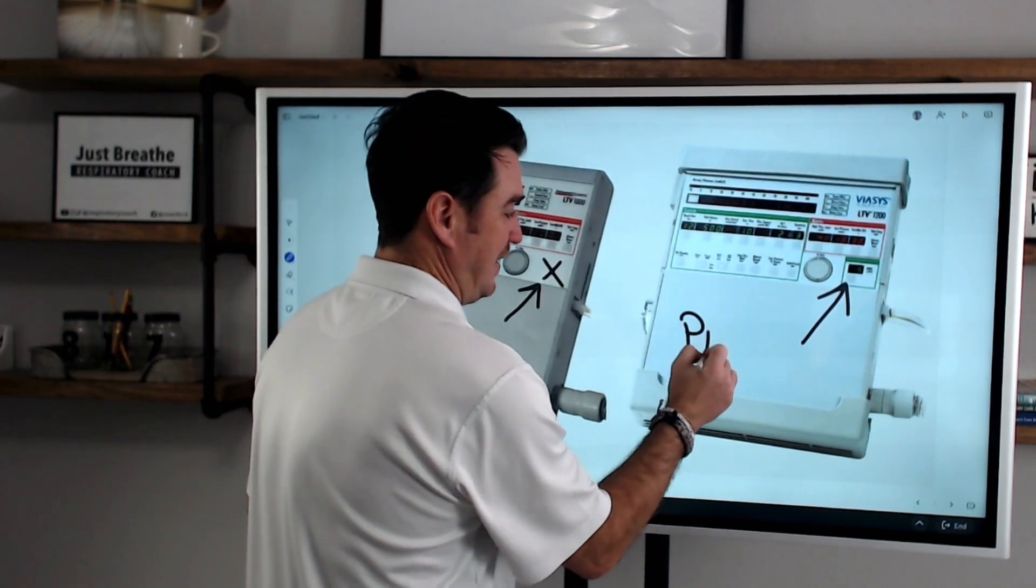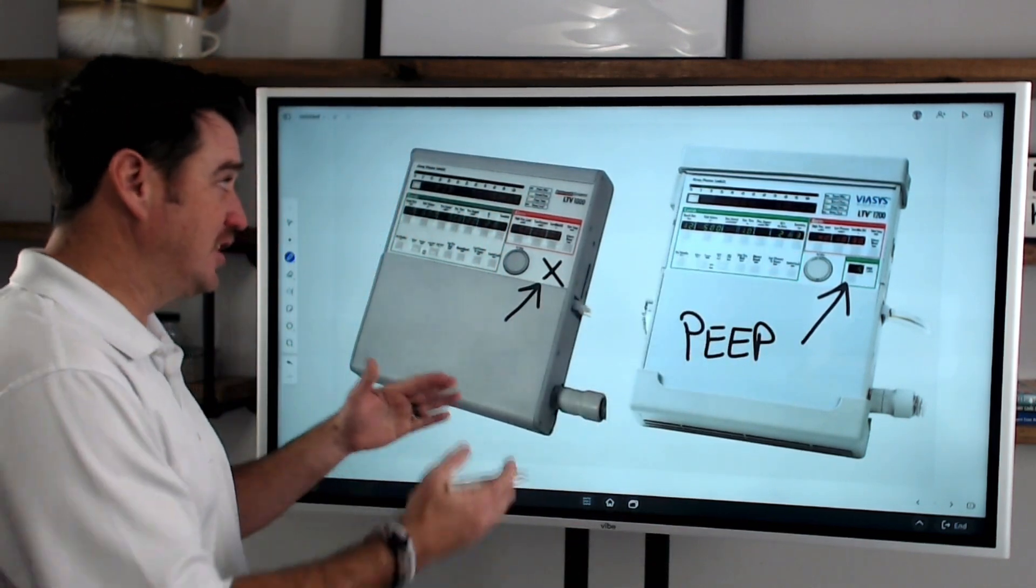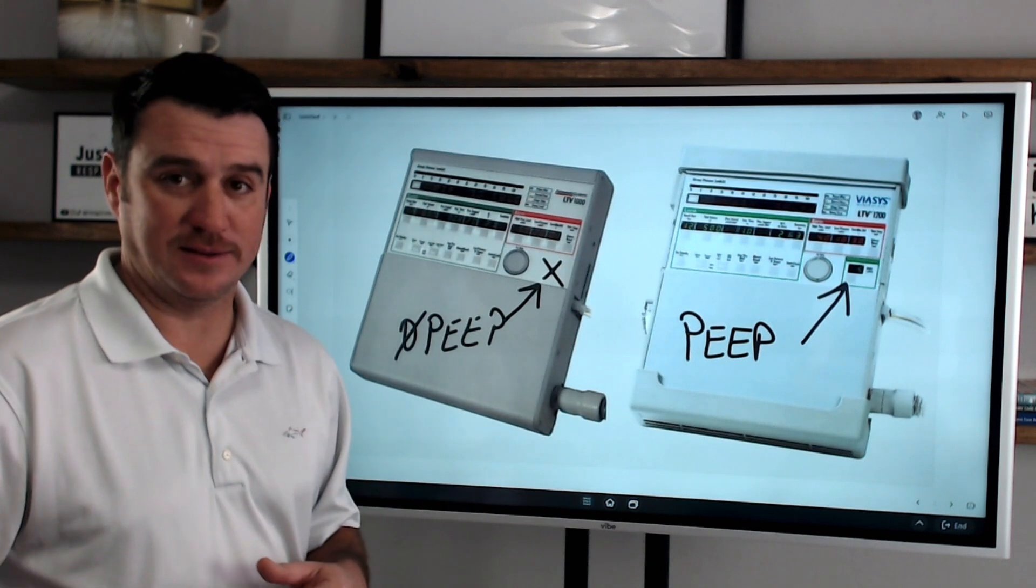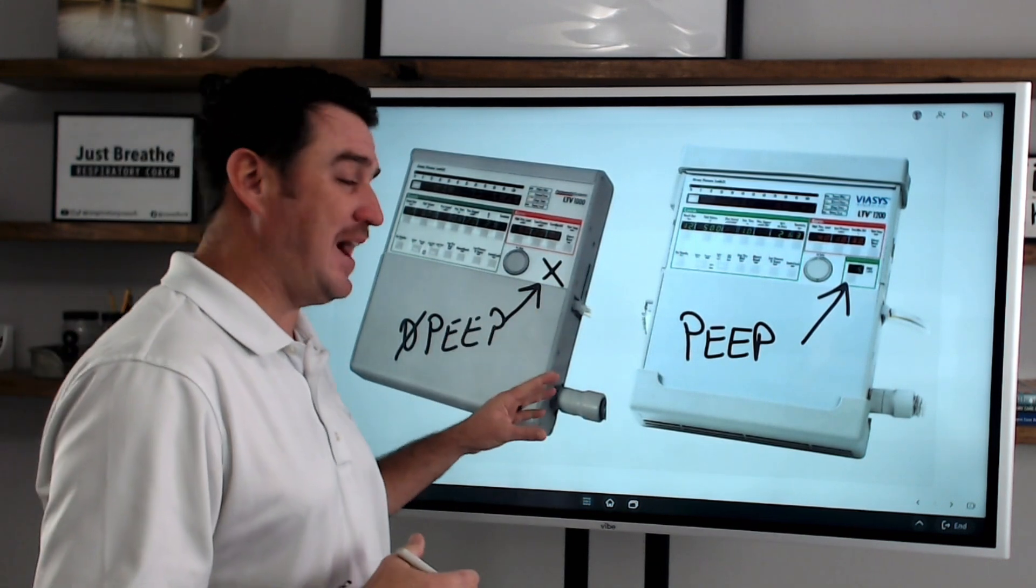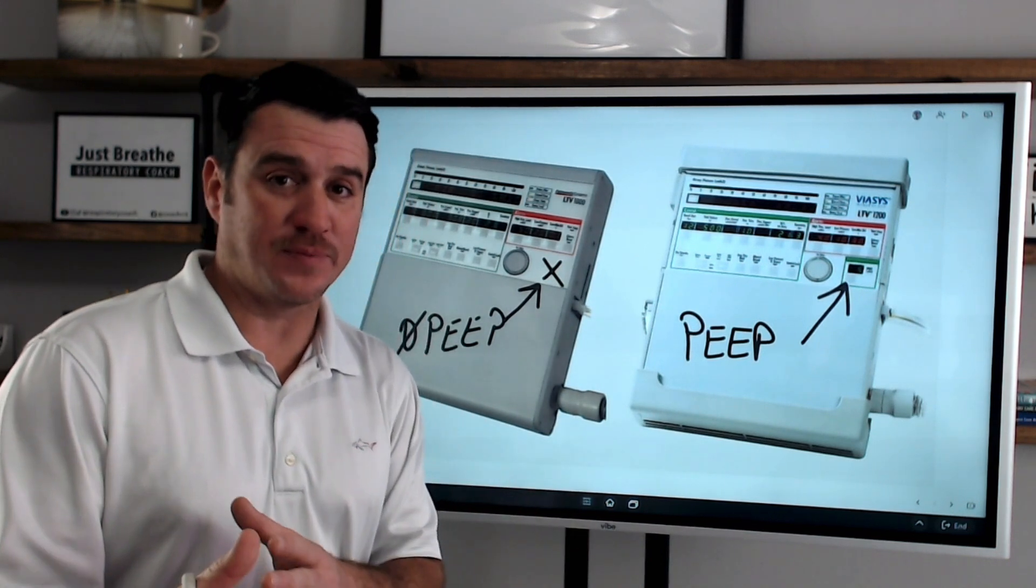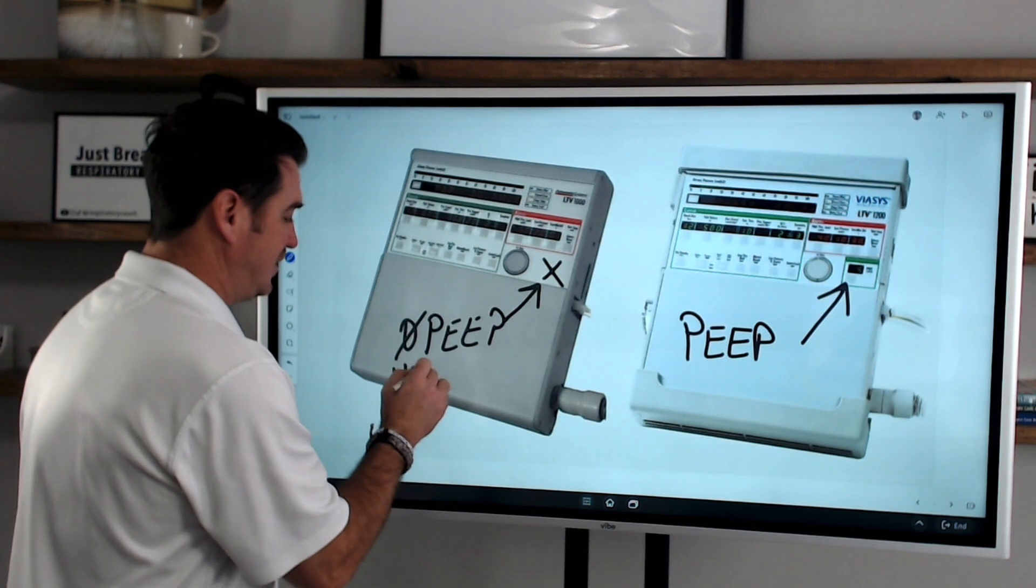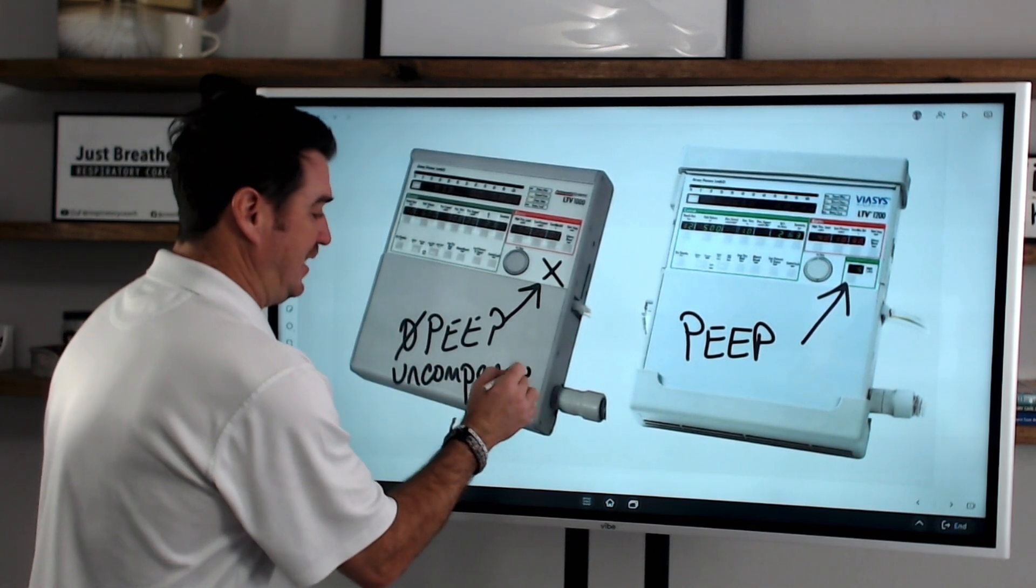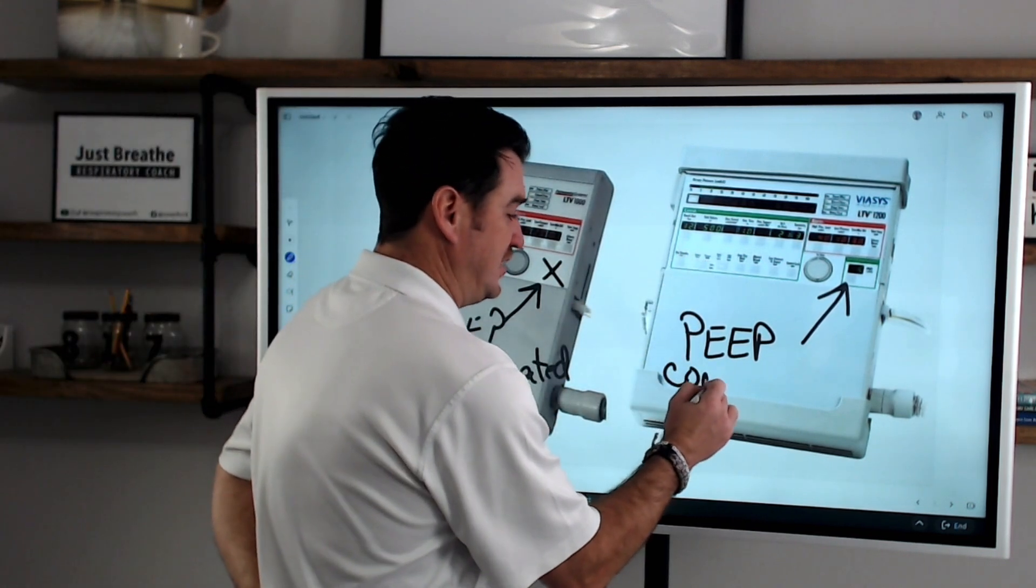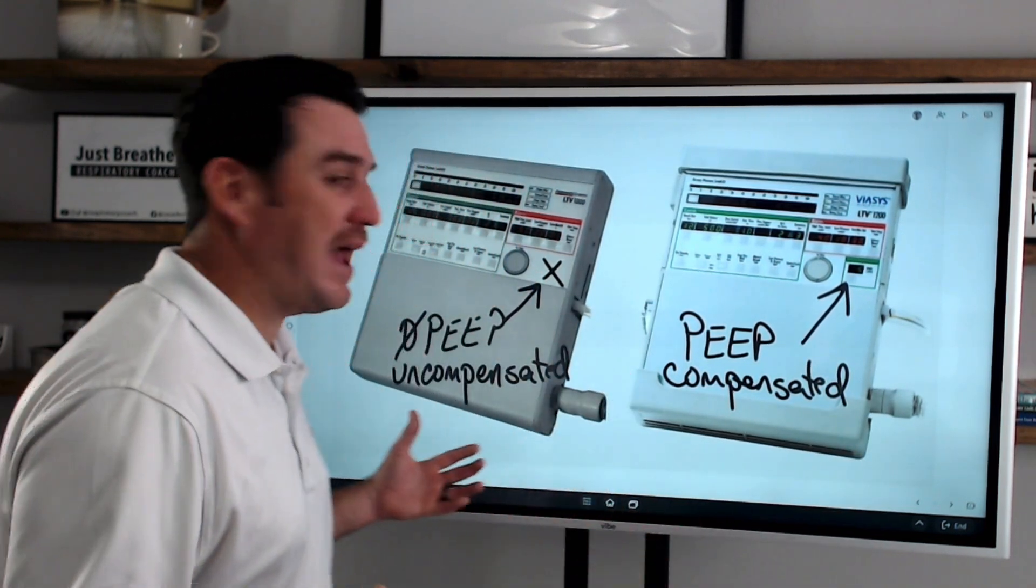This box is a PEEP setting. This is new for the LTV-1200. Now, when you look at the LTV-1000, there was no PEEP setting. Why not? Well, because the PEEP was applied externally onto the expiratory valve of the circuit. This is important because when you work with these two ventilators, you have got to understand that the LTV-1000 is uncompensated versus the LTV-1200, which is PEEP compensated. Now, why does this even matter? Well, let's talk about it.